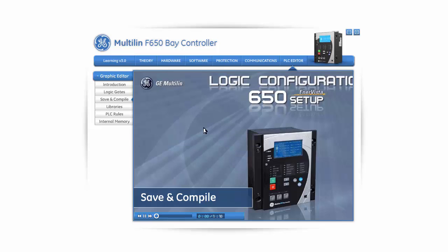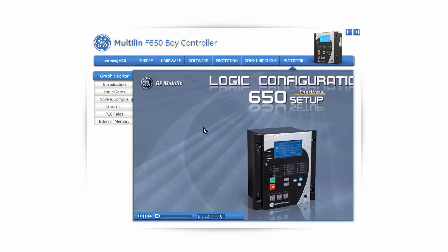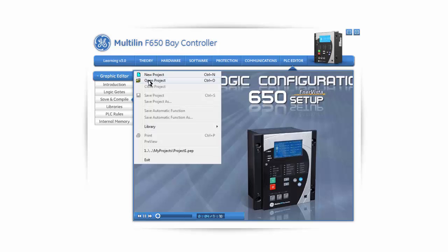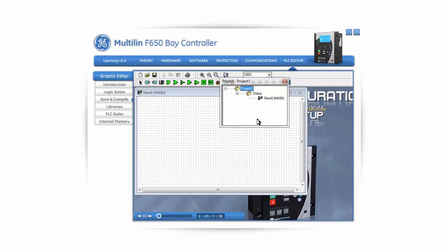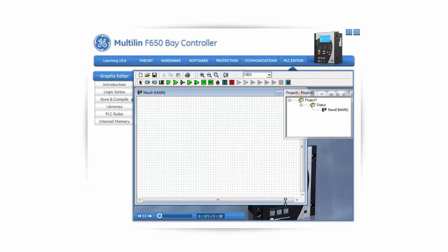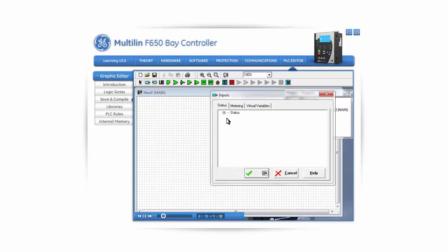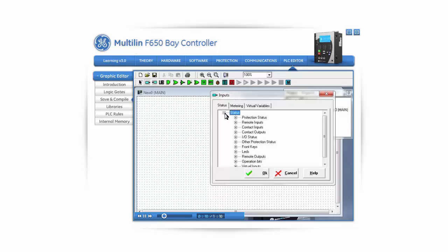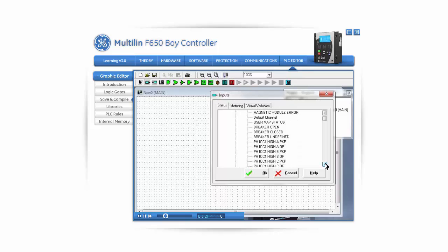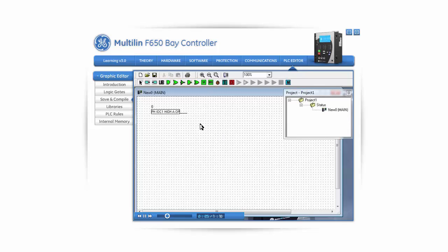In this section, we will learn how to start programming the PLC editor. We'll start with a new canvas and create our own logic. Open the 650 PLC editor as previously shown and select New Project to open a new logic canvas. Let's create a simple logic that activates a tripping signal once we have a timed or instantaneous overcurrent operation. First, we need to define the inputs. Hover the mouse over the inputs icon. Once the inputs are selected, click anywhere in the empty canvas to place the input. In the menu with all the internal flex operands, click on Status, Protection Status, then scroll down to find Phase Instantaneous Overcurrent 1 High Operate and click OK. To insert the timed overcurrent, repeat the same steps.